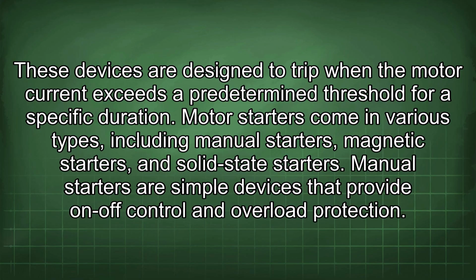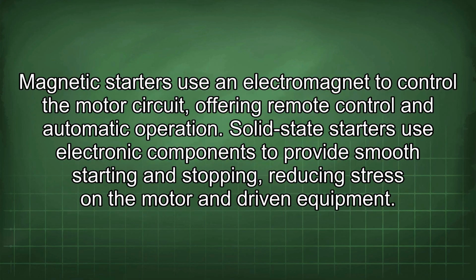Motor starters come in various types, including manual starters, magnetic starters, and solid-state starters. Manual starters are simple devices that provide on-off control and overload protection. Magnetic starters use an electromagnet to control the motor circuit, offering remote control and automatic operation. Solid-state starters use electronic components to provide smooth starting and stopping, reducing stress on the motor and driven equipment.